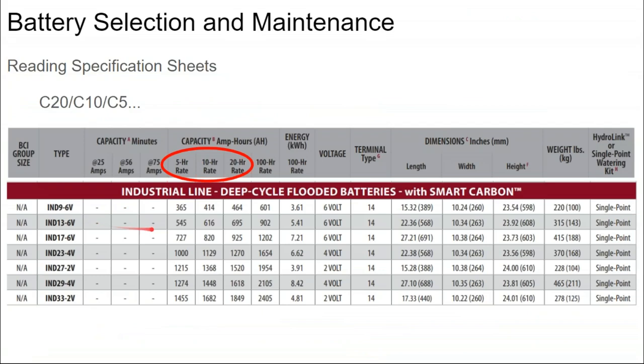Basically what they're doing here is giving you a choice between high voltage and lower amperage, or lower voltage and higher amperage. You can always add more batteries in series to increase the voltage, but this is at the bottom of the product line—as low voltage and as high amperage as they can possibly make this battery with lead acid technology.